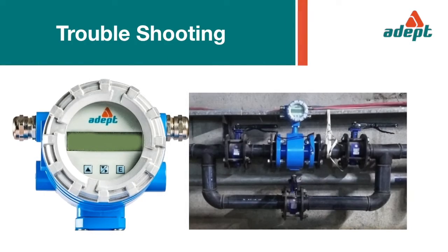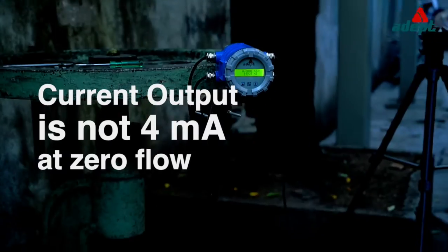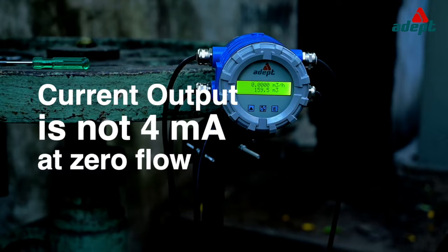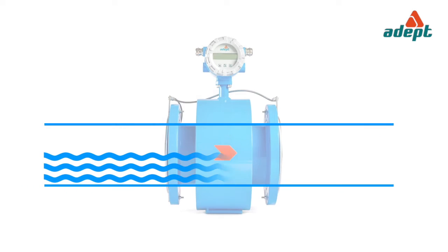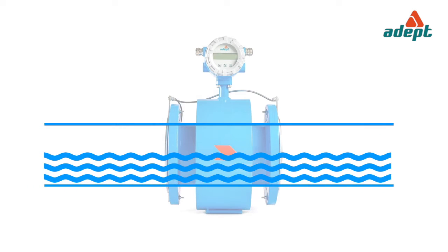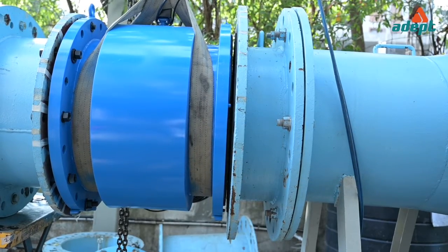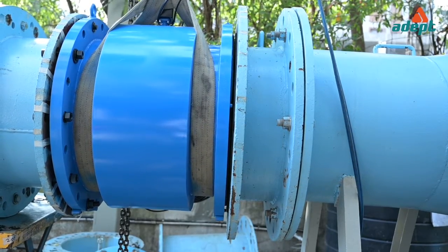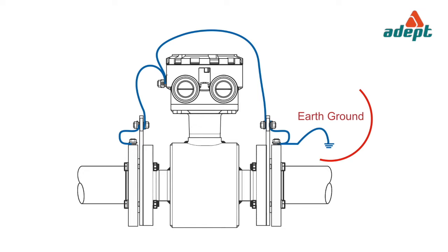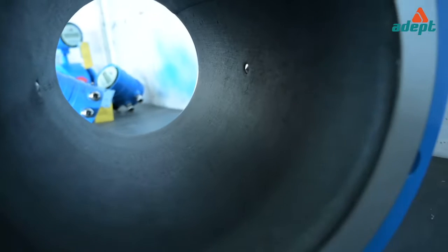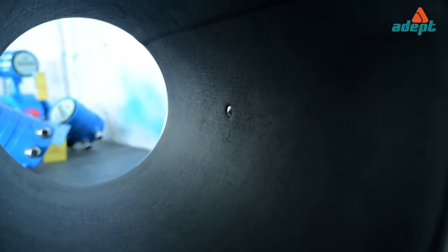Troubleshooting. Current output is not 4 mA at zero flow. Possible causes: flow is not actually zero, flow tube is not mounted correctly, grounding is not done properly, flow tube is not full, or electrodes are contaminated.